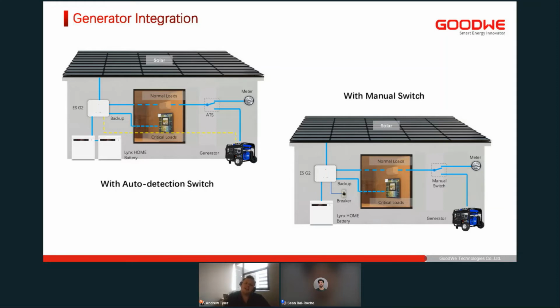And in the left example, we've got the option to send a signal to a relay to switch our generator on or off, depending on a specific software setting. So we would typically say if our batteries reach a 20% state of charge, we would then start the generator to top the batteries up. And typically you would have an ATS, or an auto transfer switch, installed, so that when the grid does fail, your ATS changes over between the grid and the generator to then charge the batteries.